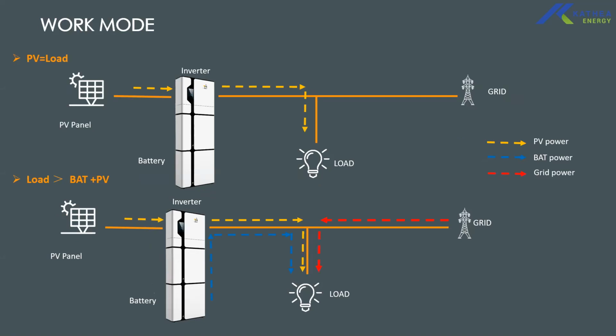If your PV is equal to the load, the system takes priority to supply your loads, or so the system would actually use your PV to supply your loads. When your load is greater than PV and battery, that's basically when your PV is less than the load consumption, so the system would use your PV to supply your loads. The deficiency it takes from the battery, depending on the battery rating. If there is a further deficiency, then it will take power from the grid to supply your loads.